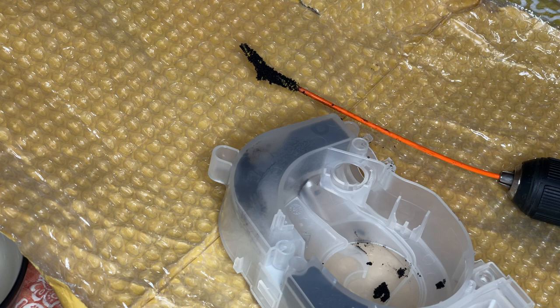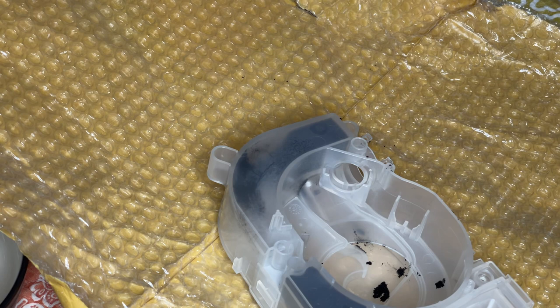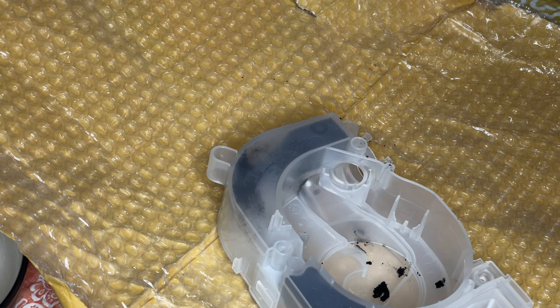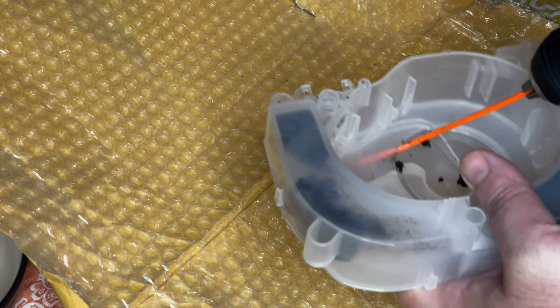Sorry about the cut there. I got really upset, to be honest with you. I thought I was going to be defoaming my dad's DreamStation so he could use it. And this is what it looks like — this is what the foam in his DreamStation has turned into. I can't even really get it out of there. The point is, you want the drain weasel to wrap around that foam, but it's so completely disintegrated. There's nothing to wrap around, there's just no solidity to it whatsoever.